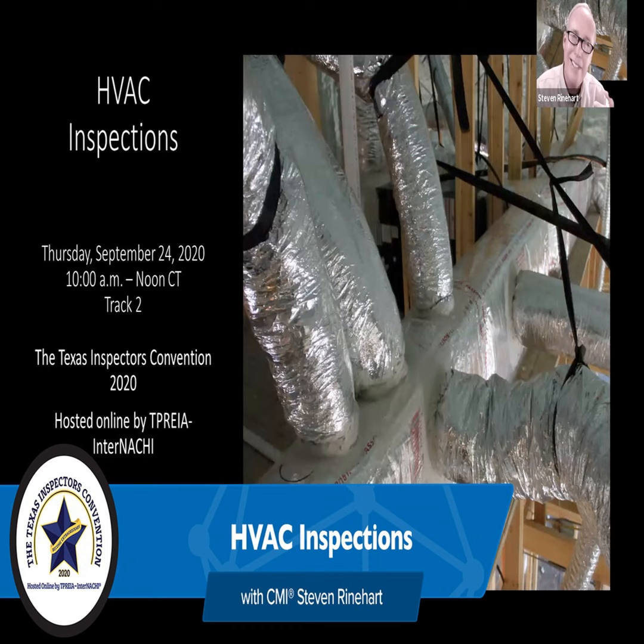They just tap into the return plenum and put an electric damper because you don't need it all the time, and they put a filter because usually it's beyond the filter, which might be in the ceiling. And you want to get it from a good clean place. You don't want to pull it from the back patio right above the stub out for the gas grill. Most people put it in, say, the front patio or in the side soffit somewhere.